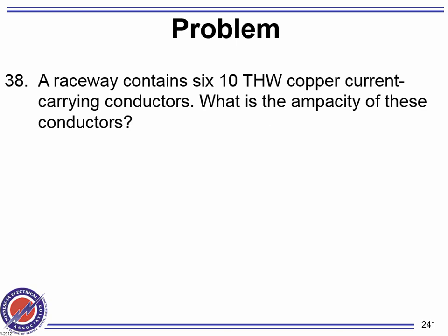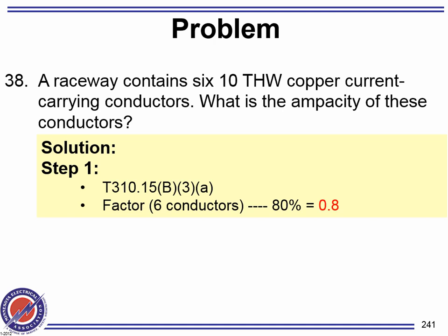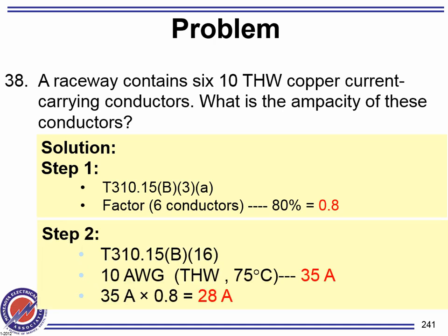What is the ampacity of these conductors? They're THW. Yeah, why not 60? Because we're derating. When we derate, guys, we go strictly by where the installation puts us. We don't worry about the normal operation, right? So how many conductors? There's six of them. So for six of them, it's 80%. Under 75 gives you 35. Then now you can't carry more than 28.